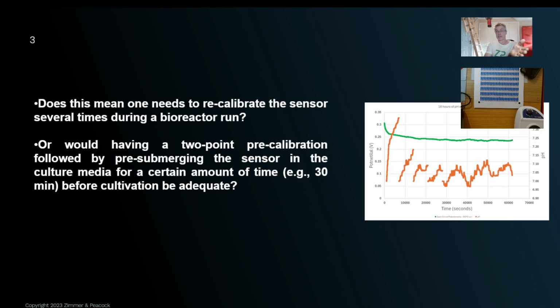Now I'm extrapolating slightly off many of our sensors, but many biosensors are made in anhydrous conditions. And so the first time they see an aqueous solution is the time that they undergo their most change. But the next time they get exposed to the aqueous solution, they've already done all the changing that they were going to do previously. So what I would say is your point 2 is a good point, but do a pre-submerge and then a 2 point calibration and then go into the reactor, and you'll probably find that fairly quickly on it will have stabilized.